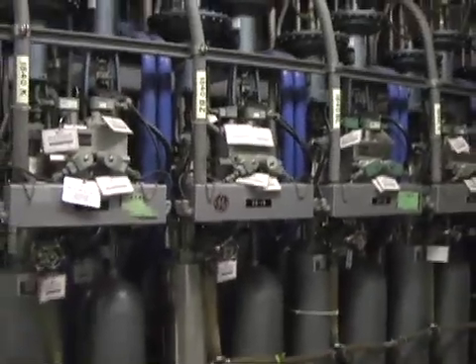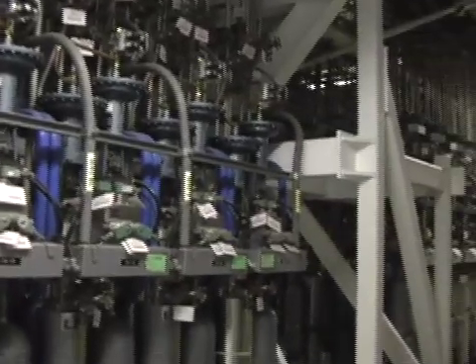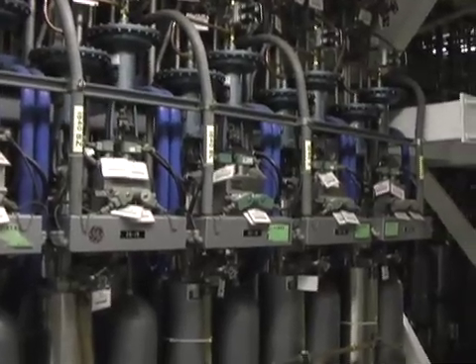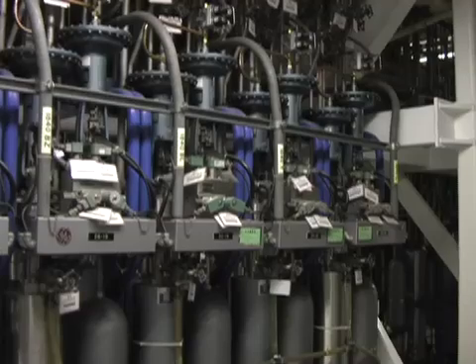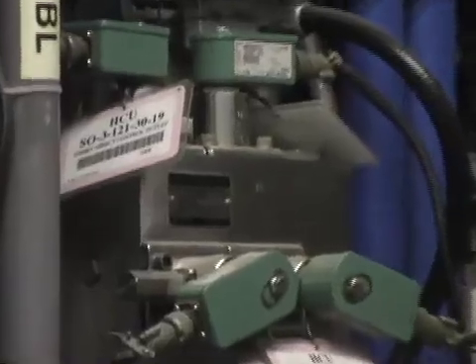These are all hydraulic control units. The reactor has 368 bundles of fuel and 89 control rods. Each control rod comes up between four bundles of fuel — that's how we control power in the reactor, with control rods and with the flow of water. More water flow increases reactor power; less flow decreases it. These units insert or withdraw the control rods from the reactor using water pressure. There's a fail-safe system — they're inserted with nitrogen if that doesn't work, and there's another system as backup. Like everything in a nuclear power plant, there are redundant safety systems to ensure you always have control of the reactor power and can shut it down whenever needed.